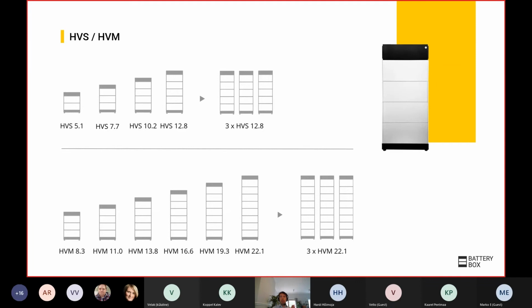The high voltage small modules are 25 amp hour, 100 volt modules. Putting 2 together in series reaches 200 volts for the small one, giving 5.1 kilowatt hours of capacity. You can have up to 5 in a single tower, reaching 12.8 kilowatt hours, and it's possible to have three towers in parallel. When you put systems in parallel for high voltage, they must have the same amount of modules per tower, because the number of modules sets the voltage of the system.